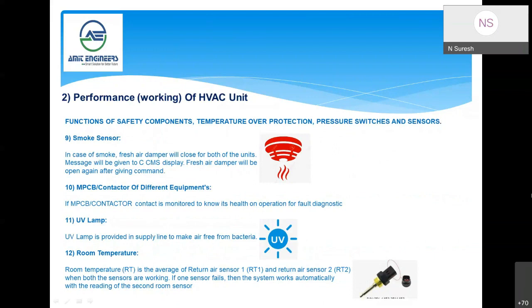Yeah, smoke sensor. This is also newly introduced in Indian Railway. In LHB it was not there, but it has been introduced in these coaches since it is a high-speed train. In case of smoke, the fresh air damper will close for both the units, and a message will be given to the CCMS display, and the fresh air damper will open again after giving a command. So in this case, only the fresh air damper will open, so that there will be dilution. The CO2 level should not increase, and within a reasonably short time, we have to take the needed action from the driver car.